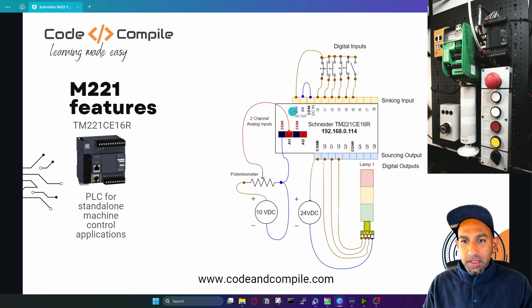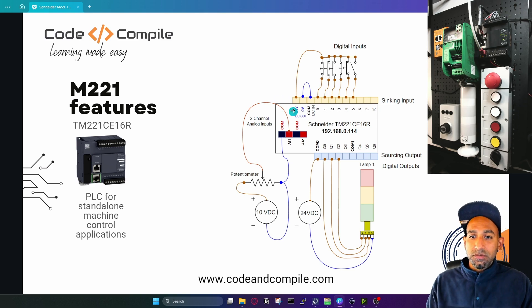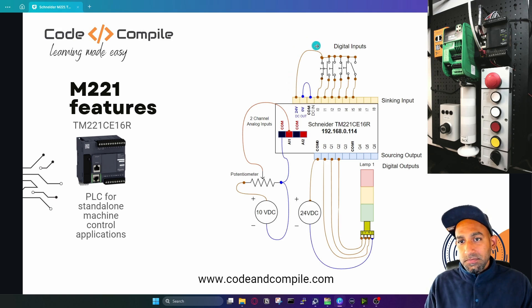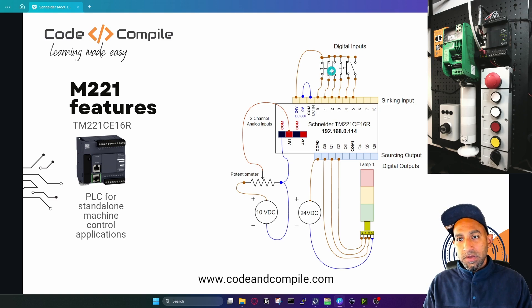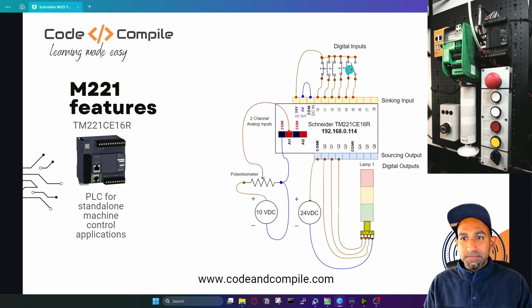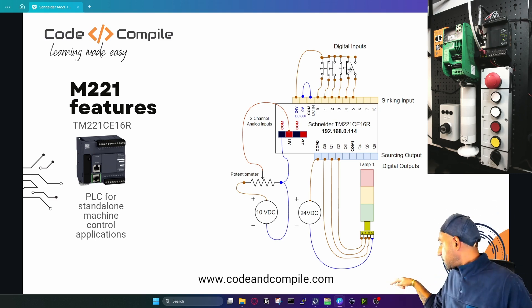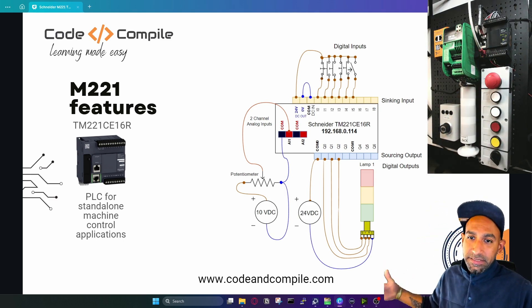On the top side we have two ports: 24 volt and zero volt — these are the DC output of the PLC. If you supply AC line and neutral to the PLC, it gives you a 24 volt output. This 24 volt output is connected to one end of the inputs. For example, you have an E-stop, then normally open push buttons, a normally closed push button, a normally open push button, and a toggle switch. When you press these buttons, they give a signal to the PLC. The E-stop is already sending a signal when it is not engaged, so my first input is already true.